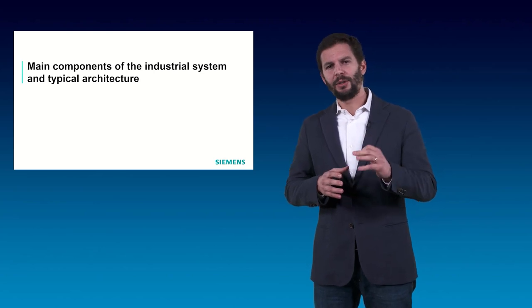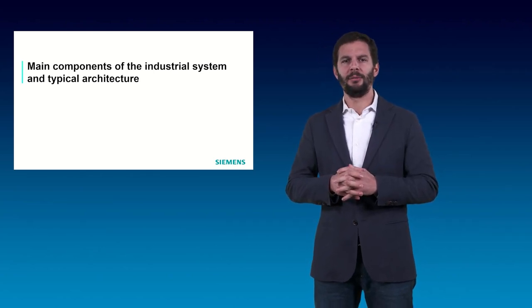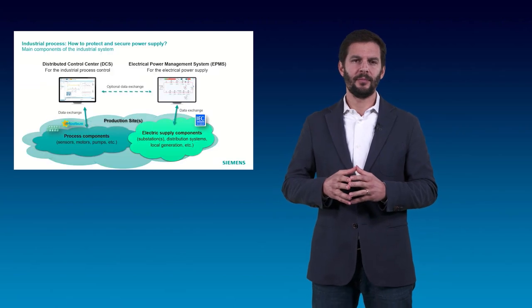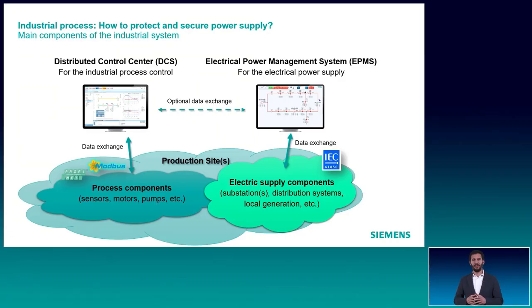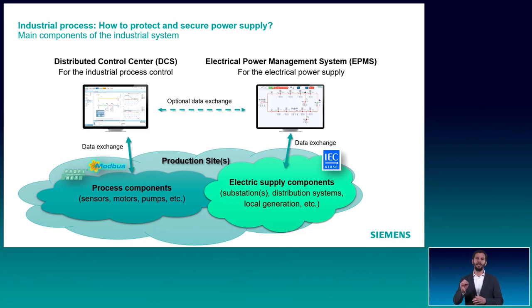Understanding the main drivers, let's take a look at the typical architecture and main components of the industrial system. As described in the picture, in an industrial facility there are two worlds. The first is the DCS, Distributed Control System, which is responsible for the main processes within the plant — for example, control of motors, pumps, compressors, etc. But when it comes to electrical energy and enabling reliable operation of the facility, we need the EPMS, Electrical Power Management System. Electrical switch gears and protection relays belong to the right side of the picture.